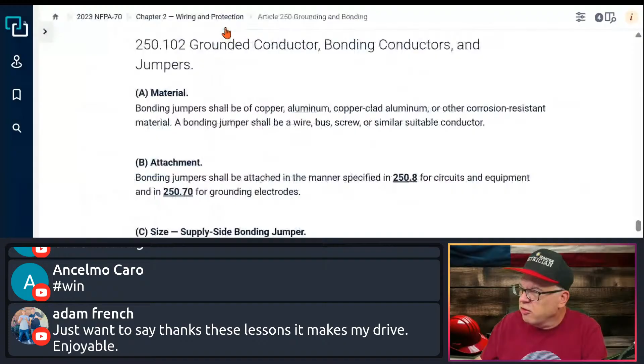So you will get those references to 250.102. And then, of course, if you're talking specifically to the application of the bonding jumpers, that would be where we had 250.102, and I will go there. I like to cover all these references so we can see them. So here's 250.102. Very familiar. We're very familiar with this. Here's your very common C. Right? This is the one we're used to, minimum sizing and things like that, right? But you also have D, which is equipment bonding jumpers. Any load side bonding, ultimately it's going to send you to 250.122 based on the size of the overcurrent device for the circuit, right? But there you go. That gives you the direction there, and here's how it sends you there.